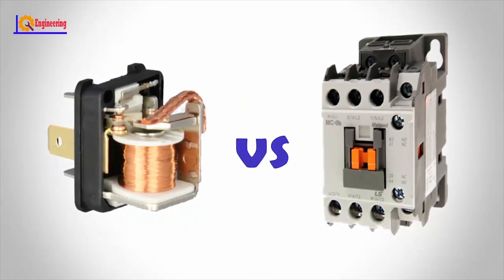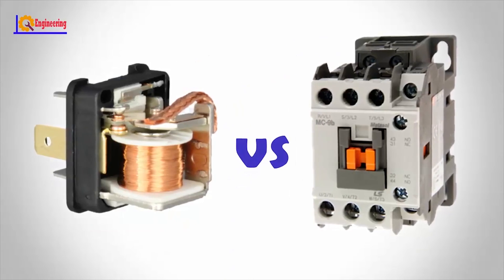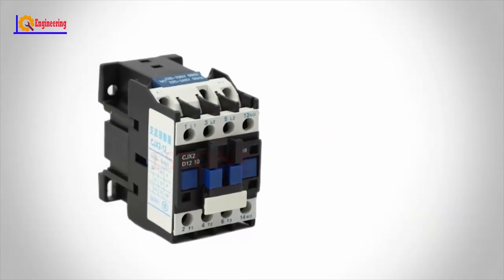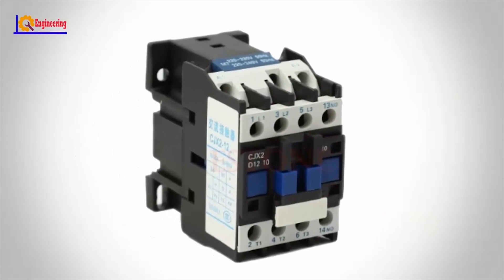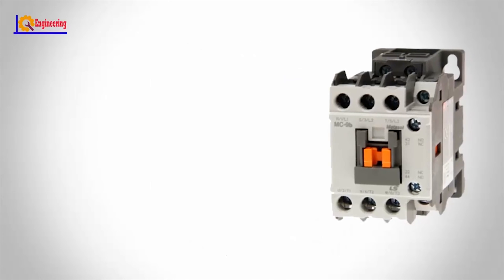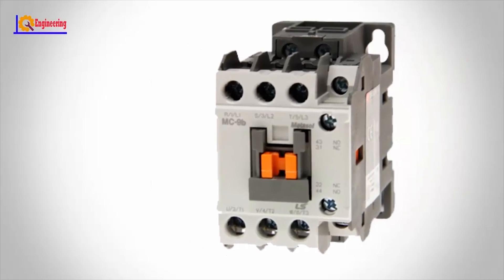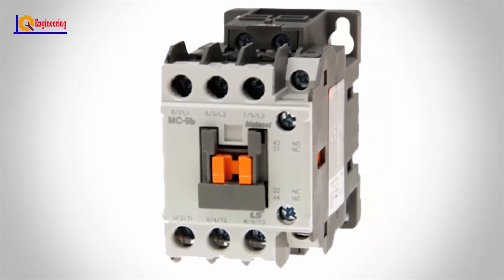The main difference between contactors and relays is the loads that they are meant to handle. Contactors are used for loads that have high voltages, high currents, or both. Contactors are used for devices that pass more than 15 amps or loads of more than 3 kilowatts.